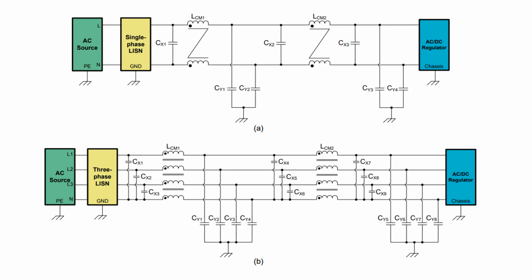Although this omits components for surge pulse protection and resistive discharge, the schematic does incorporate a line impedance stabilization network, also known as a LISN, in series with the input supply. This enables measurement of the total EMI, including DM and CM propagation components. At a higher level, passive EMI filters represent an intuitive, straightforward, and traditional approach to mitigate the conducted emissions of a power electronic circuit, even though the size, weight, and the cost of the passive components cause significant constraints in some applications.